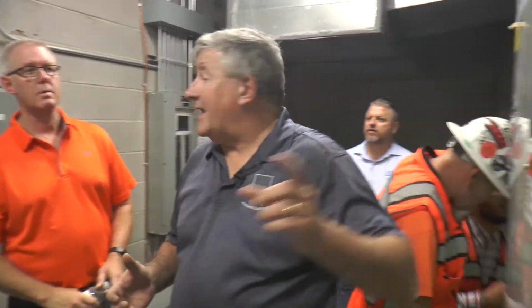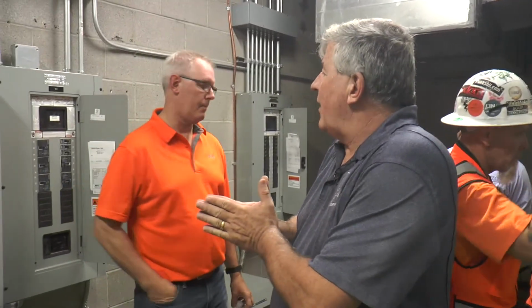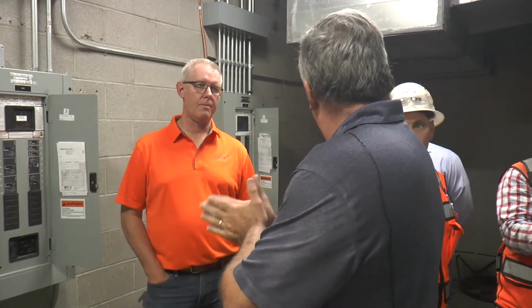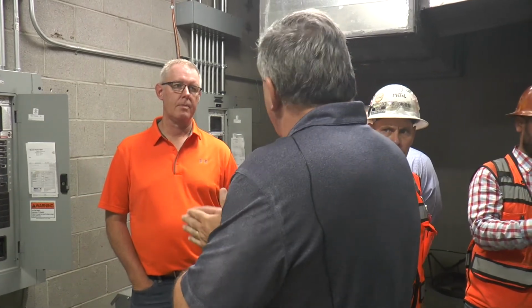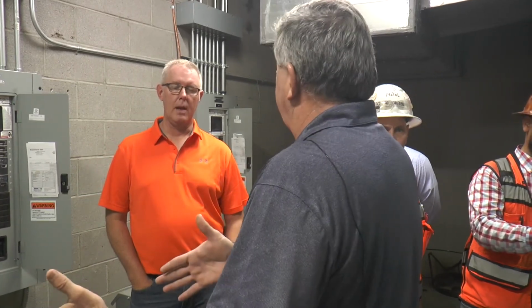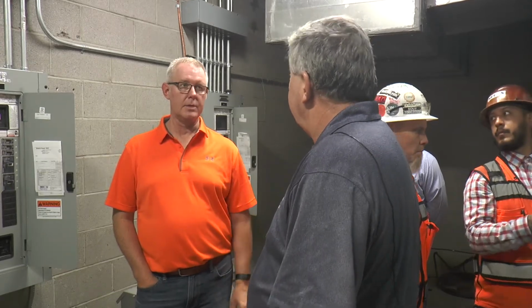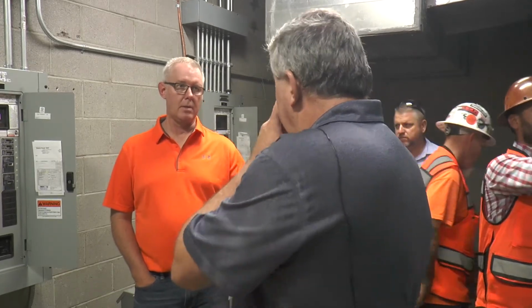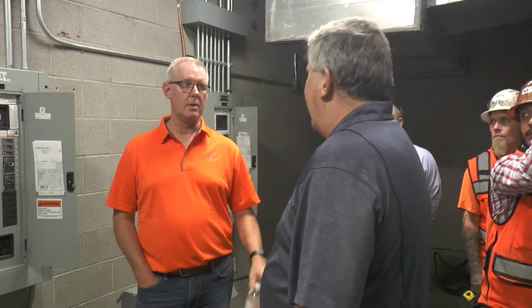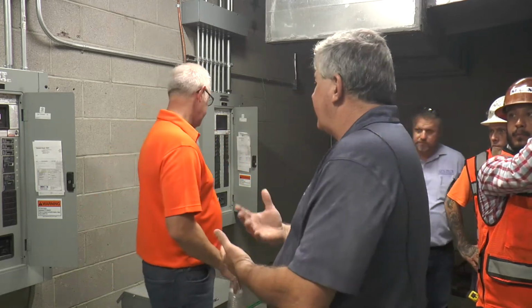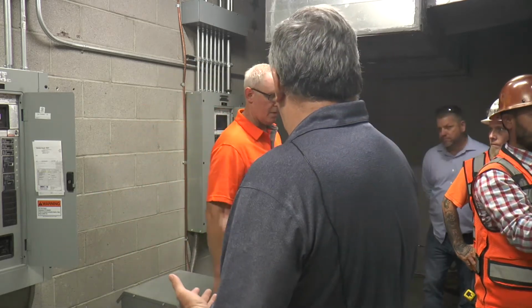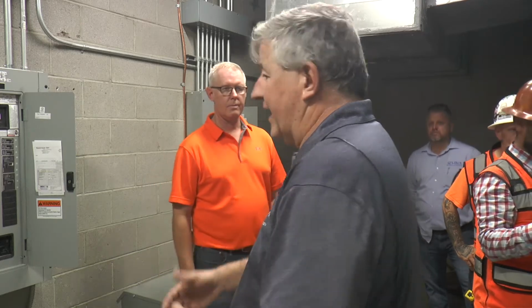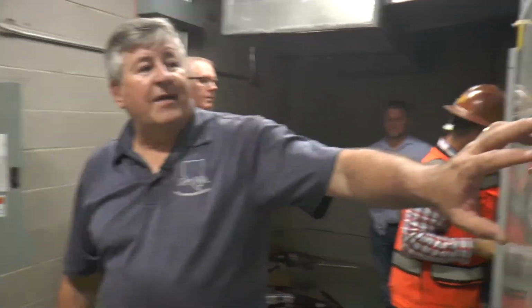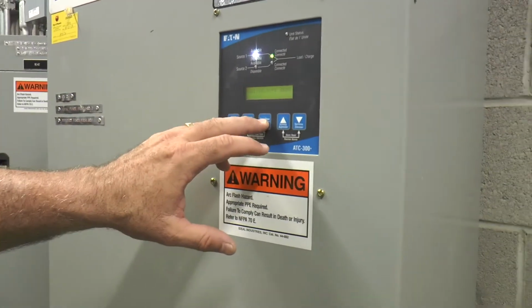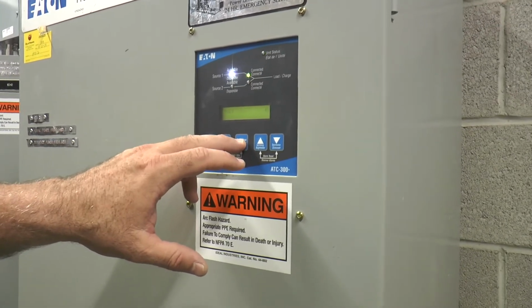Right now, it's once a week, 10 minutes. All they recommend, correct me if I'm wrong, is exercise. The duration of exercise is your discretion. I was getting into frequency, but okay, the duration's up to us. You want 10 minutes long enough to get it to heat up. Exactly. Bring it up to temperature, get the coolant moving around, get the oil moving around the top of the block, get things like that going through. Then once the timer times out, it will pre-transfer, transfer back.